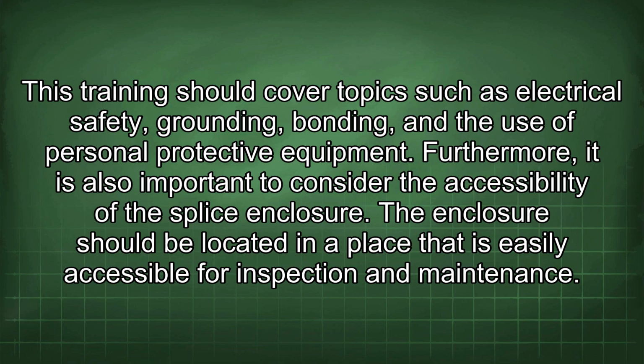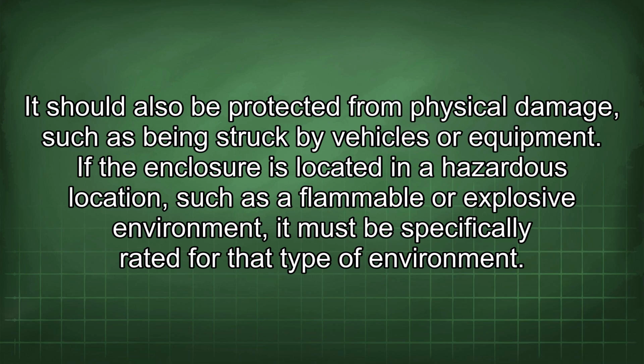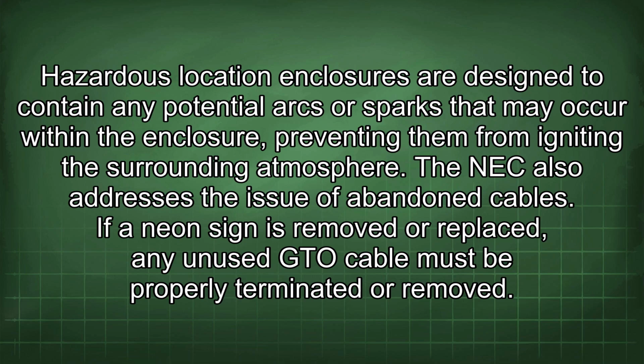Furthermore, it is also important to consider the accessibility of the splice enclosure. The enclosure should be located in a place that is easily accessible for inspection and maintenance. It should also be protected from physical damage, such as being struck by vehicles or equipment. If the enclosure is located in a hazardous location, such as a flammable or explosive environment, it must be specifically rated for the type of environment. Hazardous location enclosures are designed to contain any potential arcs or sparks that may occur within the enclosure, preventing them from igniting the surrounding atmosphere.